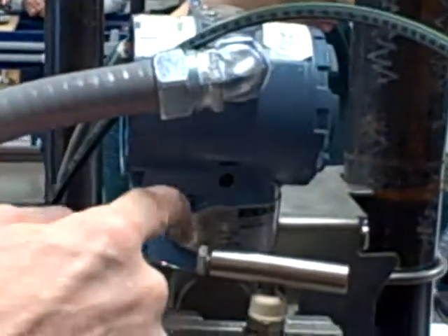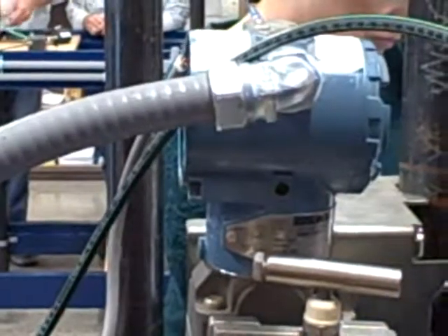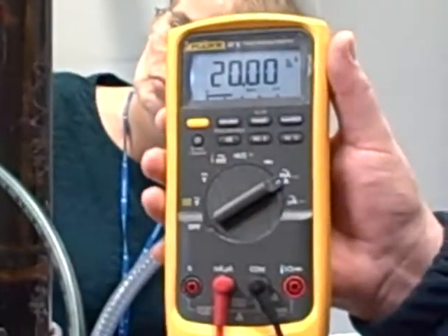But you could understand, if the D-to-A converter, the digital to analog converter, inside this transmitter were off for some reason, like a resistor value drifting or something, if the microprocessor tries to output 20 milliamps, it may not actually output 20 milliamps. Okay, I see why you did this first.